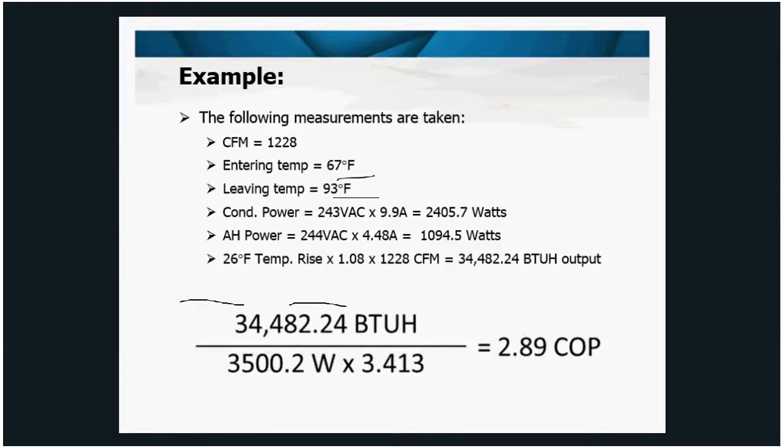2.89 times the amount of heat that I would have gotten if I put that same amount of power into an electric strip. Or you can look at it like it's 289% more efficient than straight electric heat under these conditions.